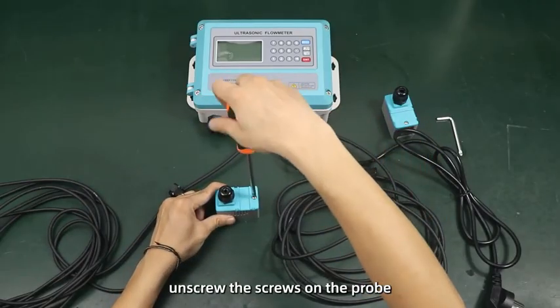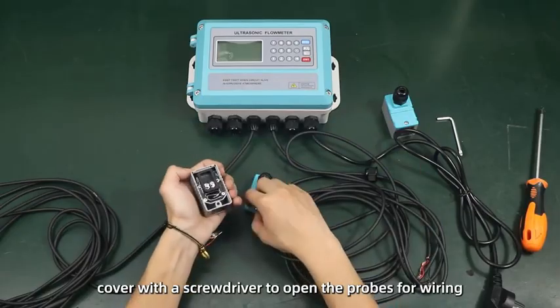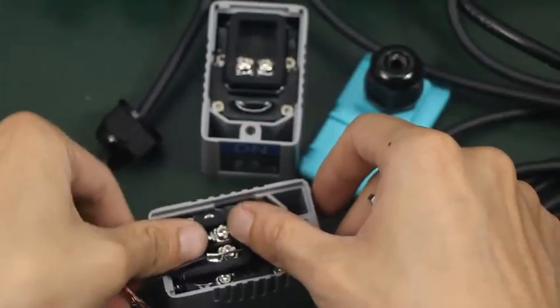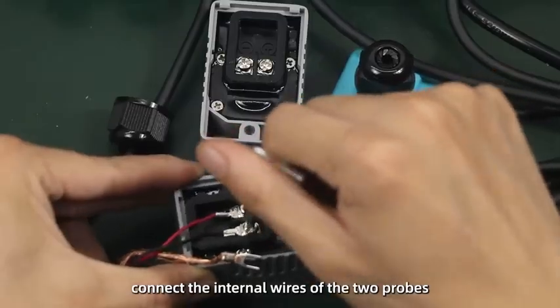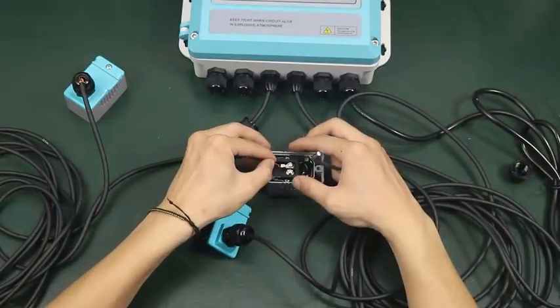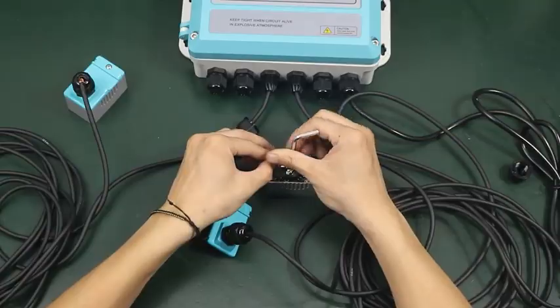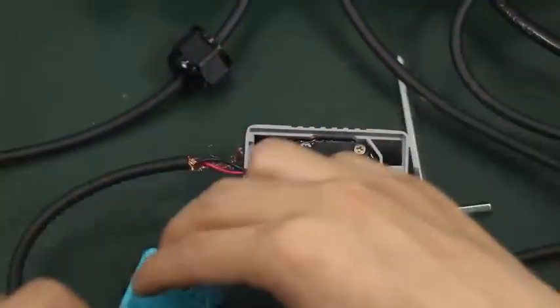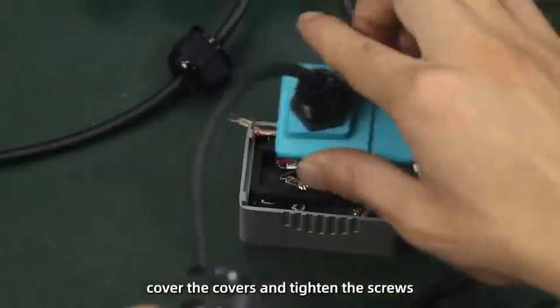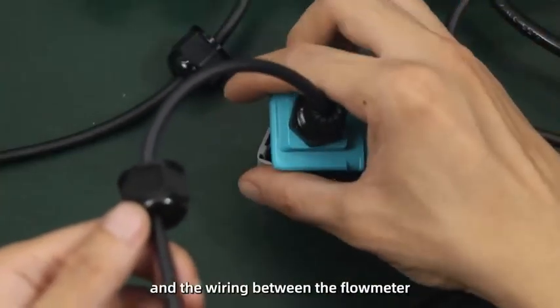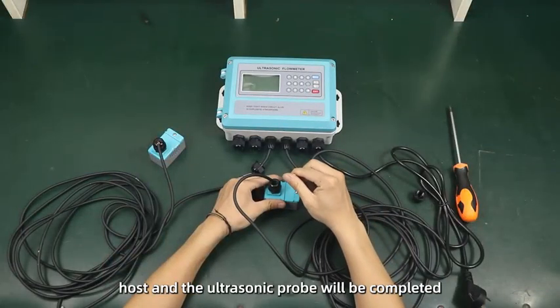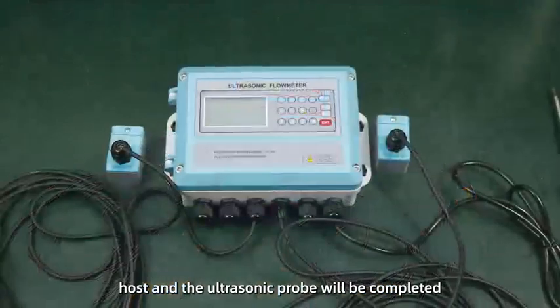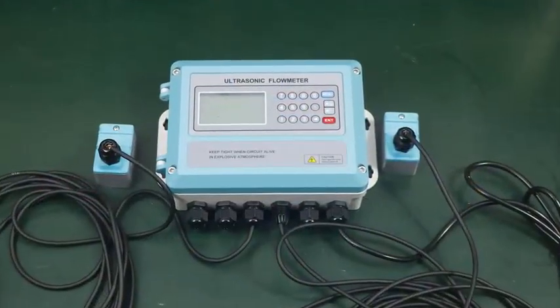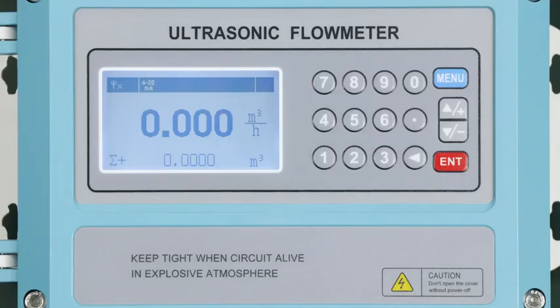Unscrew the screws on the probe cover with a screwdriver to open the probes for wiring. Connect the internal wires of the two probes in sequence. Cover the covers and tighten the screws, and the wiring between the Flowmeter host and the ultrasonic probe will be completed.